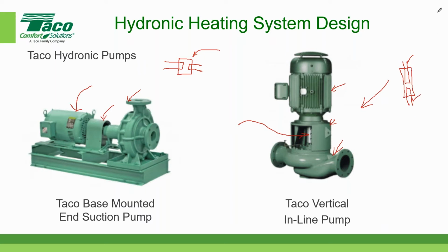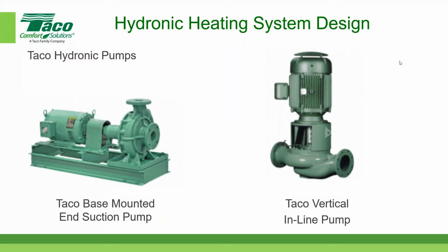There is a good question. Would you recommend any mechanical seal difference between a chilled water or a hot water pump? In general, for the temperatures and pressures that we typically run for HVAC systems, the seals are the same for both chilled water and hot water. We can provide high temperature hot water, let me rephrase that. We can provide seals that are designed for high temperature hot water systems. So yes, there are some variations for those components.